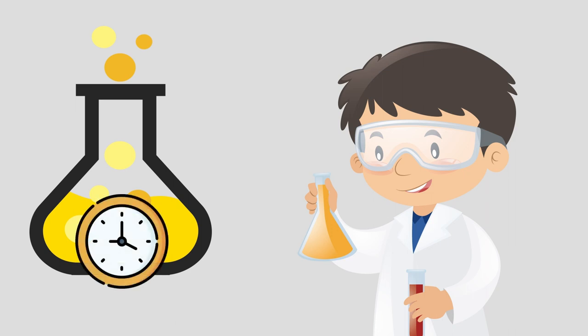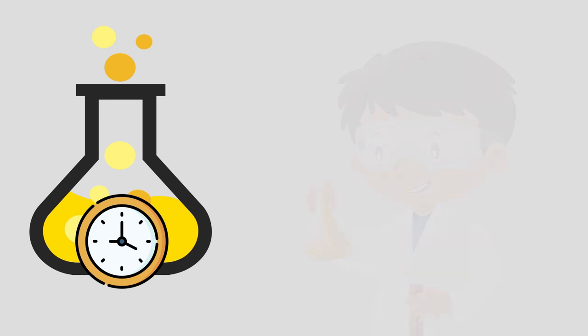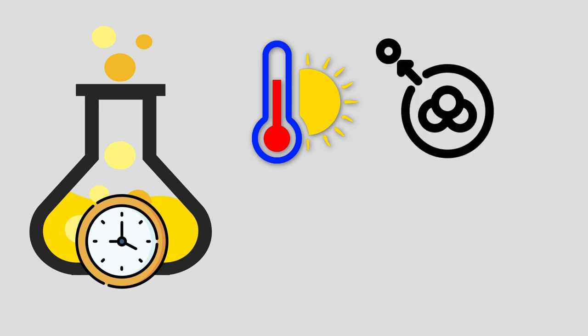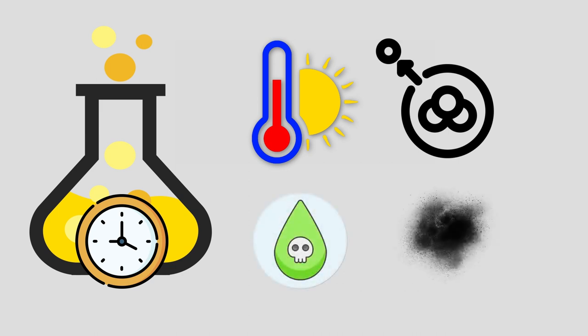In particular, turbine oils shall have high resistance against air oxidation at elevated temperature, high demulsifying ability, low initial acidity and ash content. Furthermore, no particulate matter is allowed.